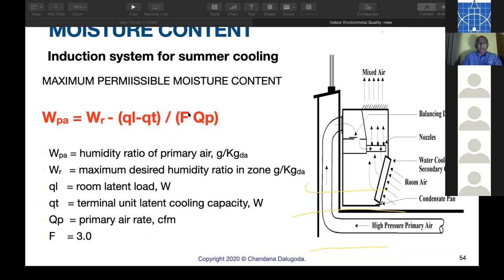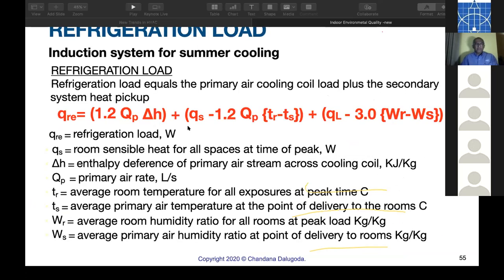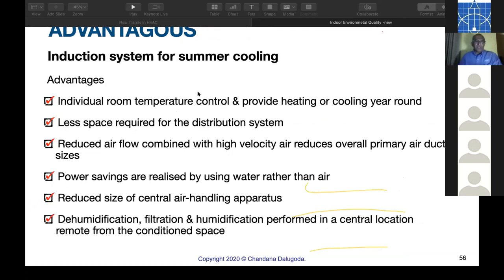This is how induction system works, and maximum possible moisture content we can calculate, because we need that moisture content low in order to absorb water vapor in the air. We can find the refrigeration load by this equation if you like. Induction systems advantages: individual room temperature control and providing heating or cooling year round. Less space required for distribution systems. No large ductwork. Reduced airflow combined with high velocity air reduces overall primary air duct sizes. Power savings are realized by using water rather than air. That is, of course, we have proved that. Reduced size of central air handling apparatus. Dehumidification, filtration, humidification performed in central location.